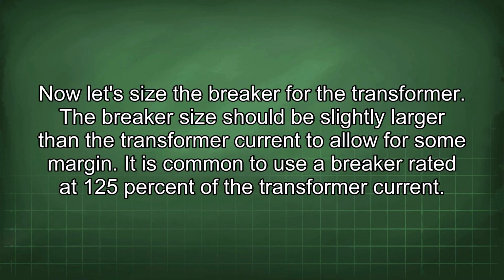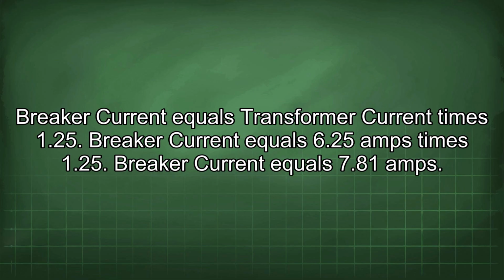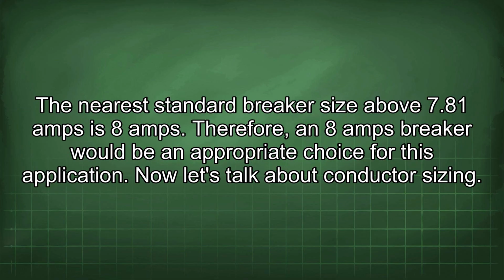Now let's size the breaker for the transformer. The breaker size should be slightly larger than the transformer current to allow for some margin. It is common to use a breaker rated at 125% of the transformer current. Breaker current equals transformer current times 1.25. Breaker current equals 6.25 amps times 1.25. Breaker current equals 7.81 amps. The nearest standard breaker size above 7.81 amps is 8 amps. Therefore, an 8 amps breaker would be an appropriate choice for this application.